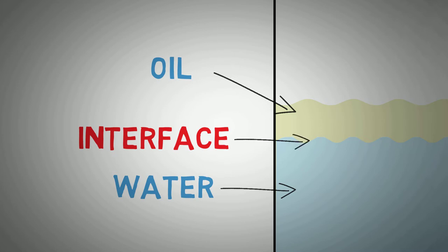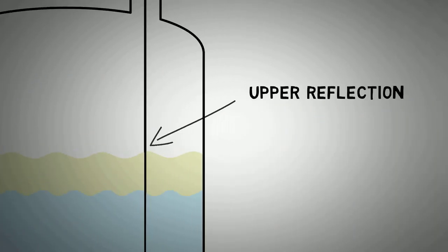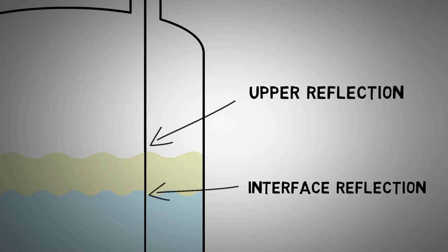In an interface setup, when the pulses hit the top layer of the media, some of the energy is reflected to give the upper measurement. However, some of the energy carries on through the upper level and onto the interface level. These remaining waves are then reflected just like the upper level. This signal can then be converted into a level measurement for the interface.